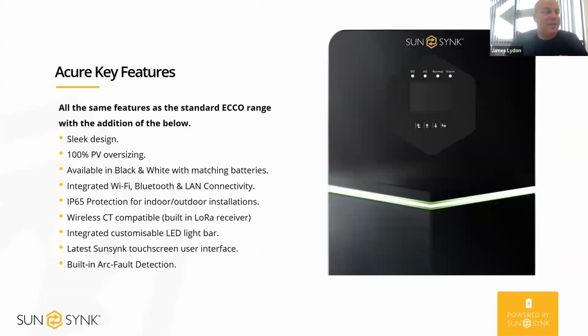Okay, so the key features of the Acure. The same as the ECCO range, sleek design, 100% PV oversizing on the Acure range. As we progress into the range, the majority of our inverters do have 100% PV oversizing. We've also got the increased max input current on the strings, just for today's larger panels. As I said, available in black and white with matching batteries. The Acure has got integrated Wi-Fi, Bluetooth, and LAN connectivity as standard. So with the previous range, you had the separate Wi-Fi logger that would connect underneath the inverter. The Acure has these built in.